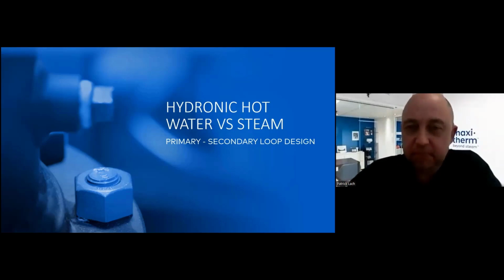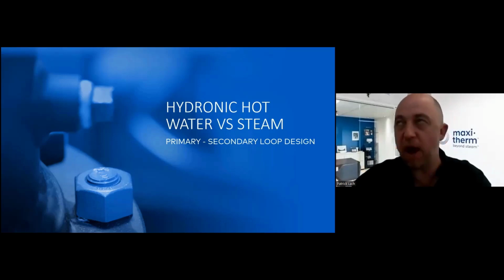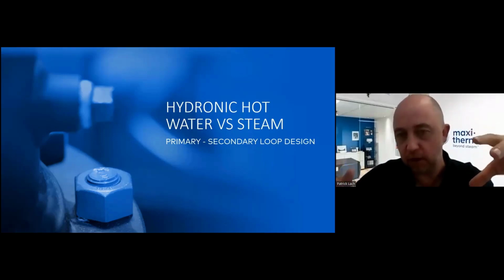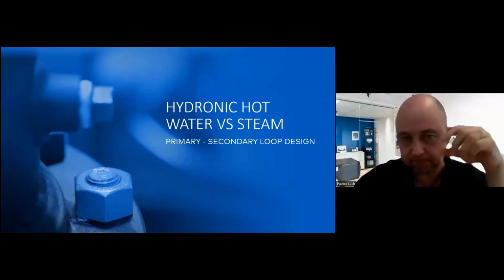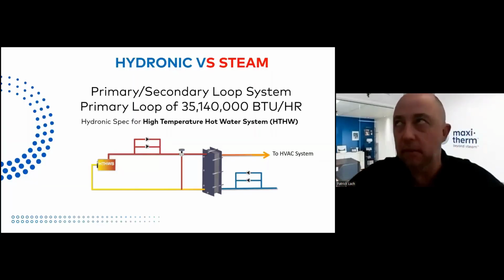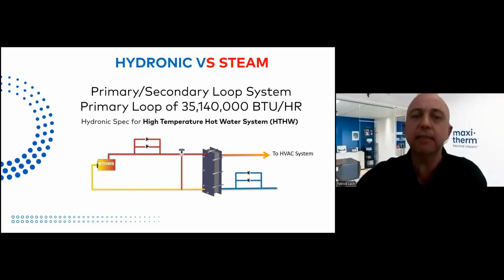Thanks, Patrick. All right. So let's move on to compare a primary loop, high temperature hot water versus steam, right? Those next slides were based on, I don't know how many years ago, maybe close to 10 years ago now. Time goes by so fast. It was a federal project design in New York State, and they decided to go high temperature hot water on the primary loop. In every mechanical room, they put the secondary loop together with a heat exchanger like this. So they could have considered going steam here on the primary loop, but they decided to go hot water.